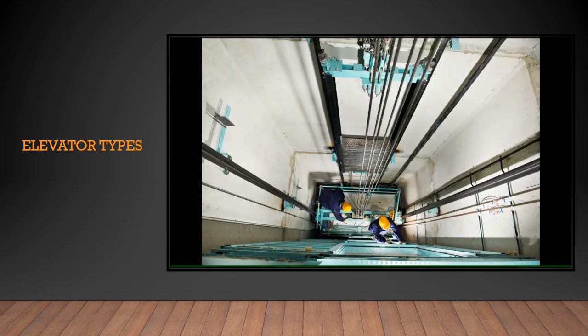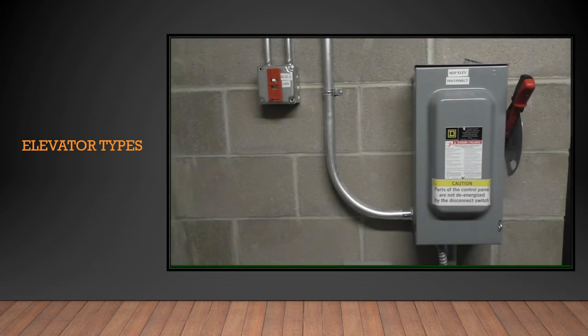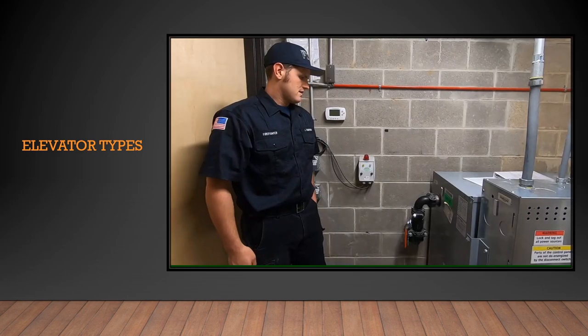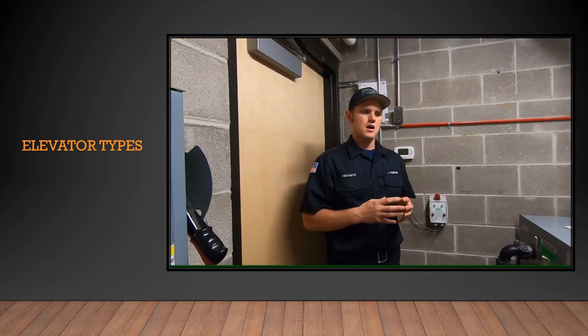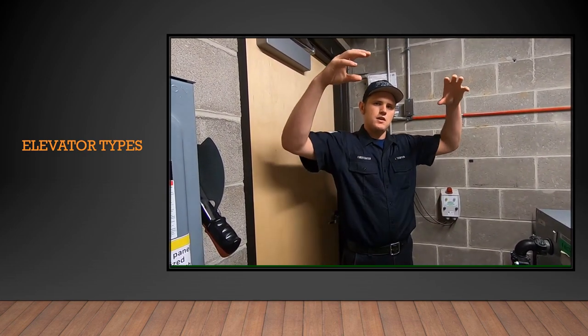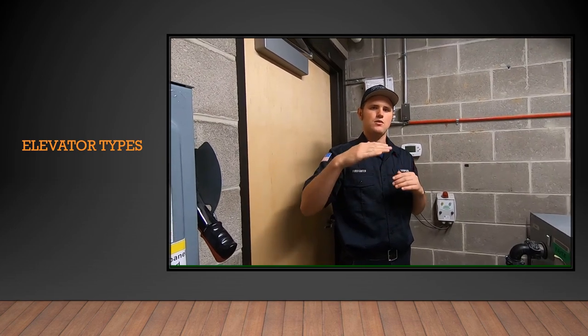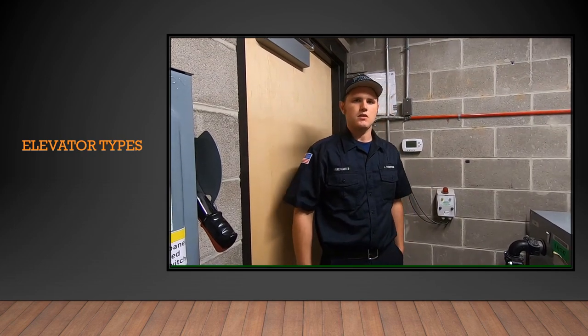In taller buildings, elevators are typically traction elevators. Traction elevators are hoisted up the elevator shaft with cables from the top of the elevator car. The traction elevator machine room is located in a room above the elevator shaft, so crew members assigned to controlling power will need to access the top floor and look for a room above the elevator. If you have a traction elevator, you usually have a penthouse where the cables, motors, and sheave sit above the elevator — usually a floor above the last floor the elevator rides on, or possibly a couple more floors above depending on the building's engineering.